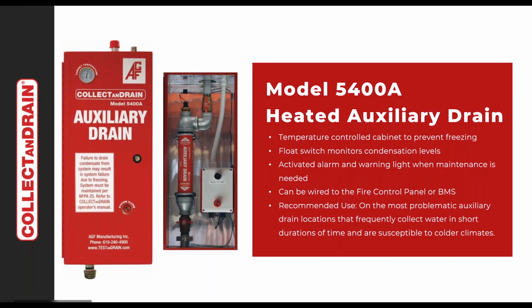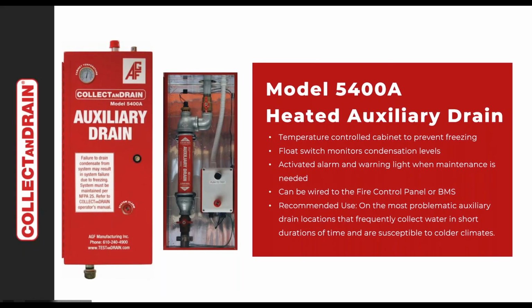So with the units that we've talked about, one of the things NFPA 13 talks about is heat protecting your low point drains to prevent them from freezing and breaking, because it is just that much of a known problem. So we introduced the model 5400A. It's a heated low point drain. It comes in a heavily insulated heated cabinet that is lockable. All units come key alike. It has the same feature of a chirping and blinking alarm once the unit is approximately 80% full. It uses a float switch.